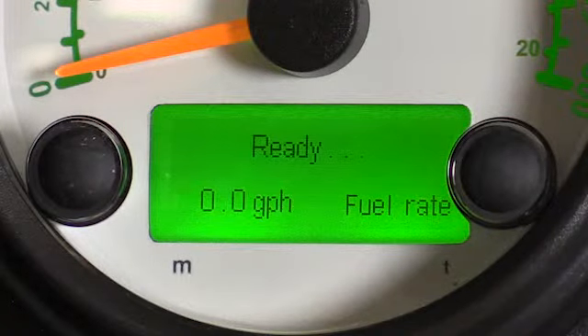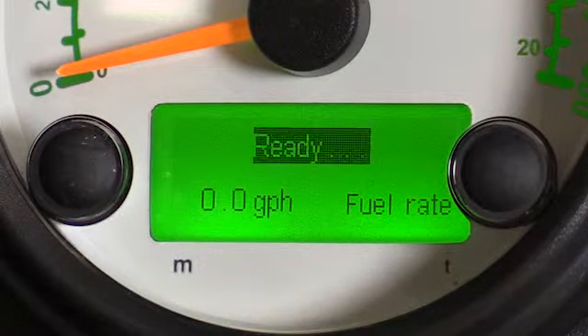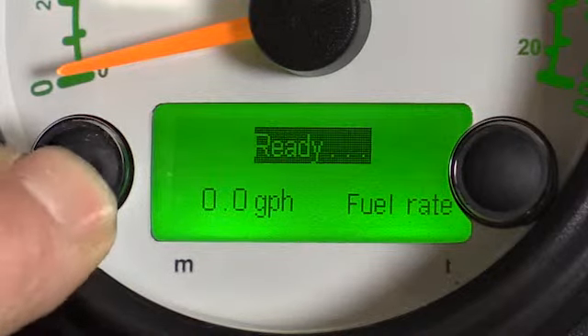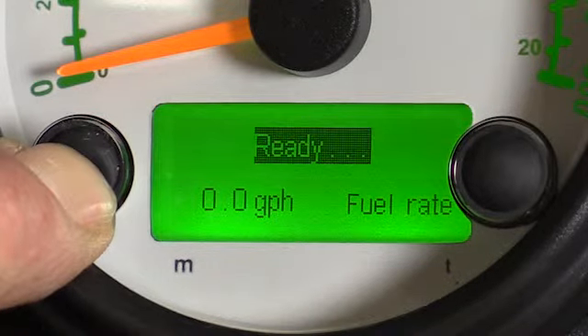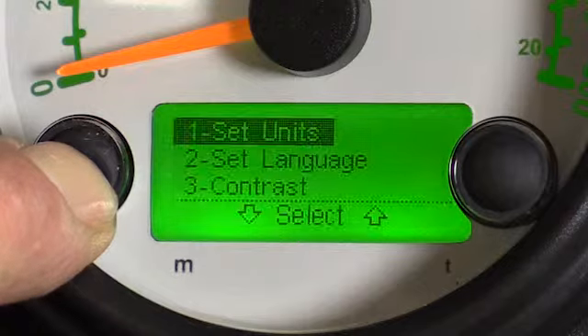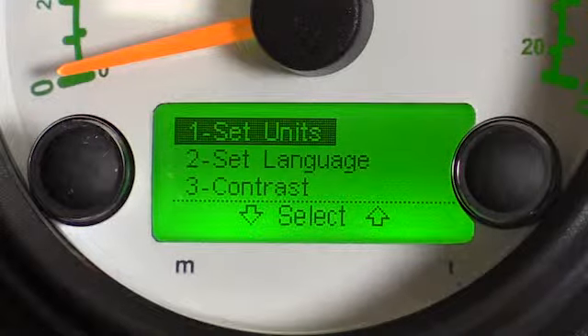While the single axle controller is in any mode, pressing the M button for more than 5 seconds brings up the Settings and Diagnostic menu screen. Navigate the menu items using the M or T buttons until the desired item is highlighted. Simultaneously press the M and the T buttons to select that desired item. 5 seconds of inactivity exits the menu. There are 8 items on this menu.